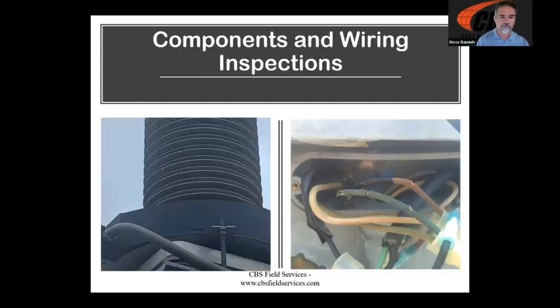I always like to hit on the fact that it's about the basics, right? When was the last time you opened up some covers on your transformers looking for bad wiring? Walk around. Do not walk past things that are just out of the ordinary, right? A crack in your CT is not normal. And if you begin to normalize it, you're going to lead yourself into danger. So once again, look for things like this and then take action.